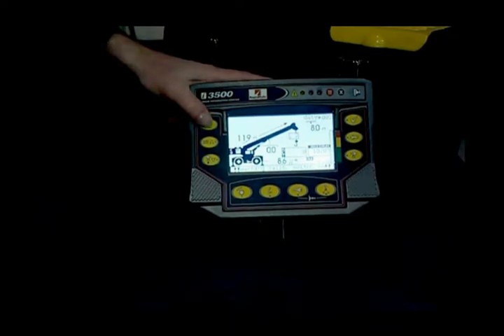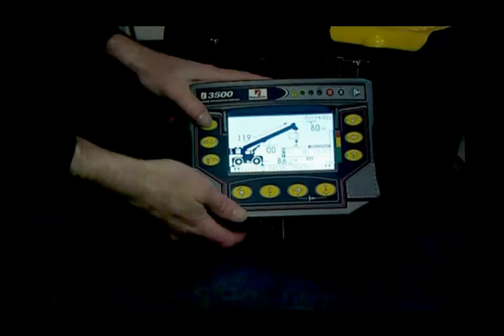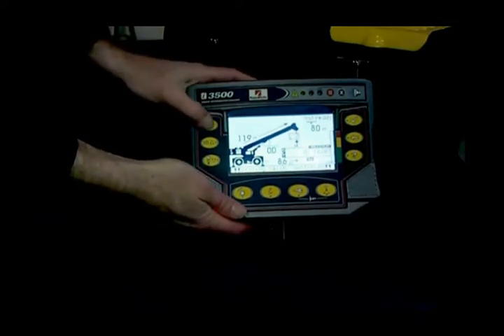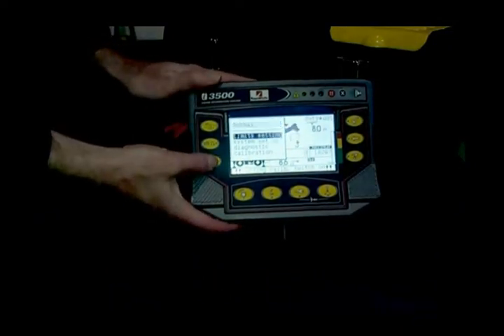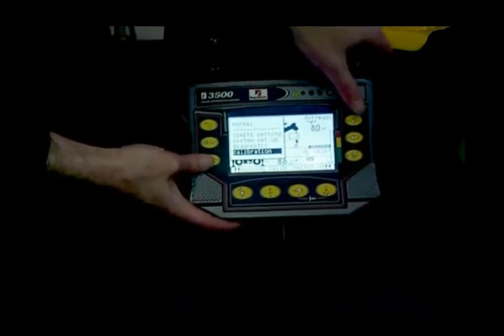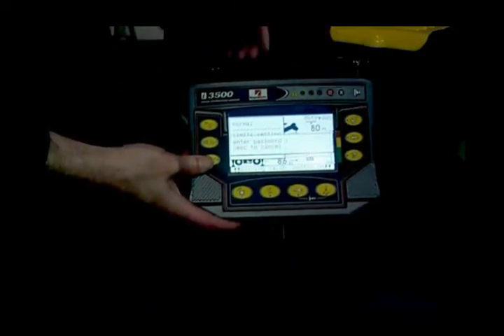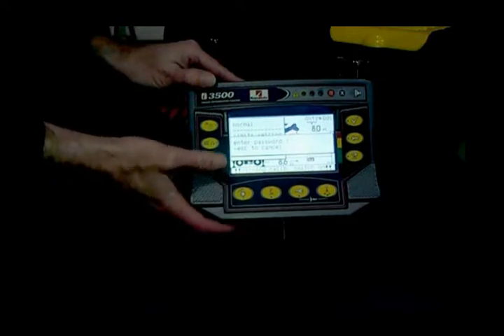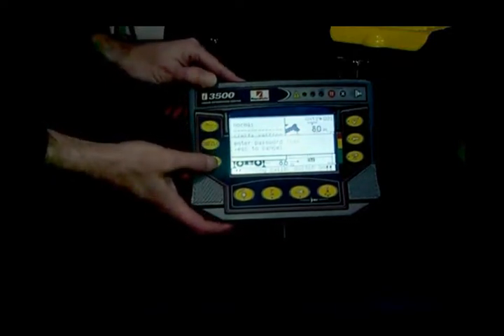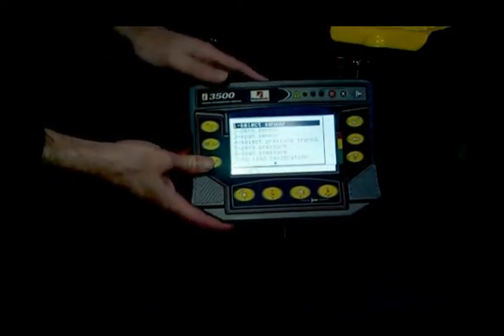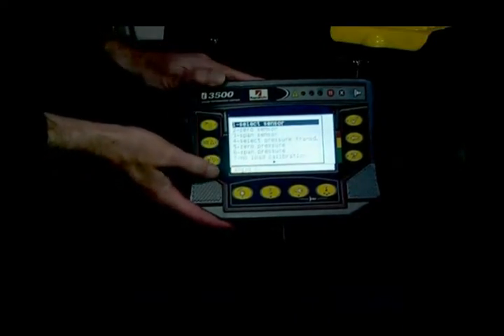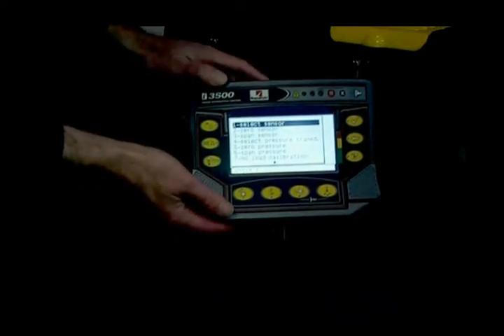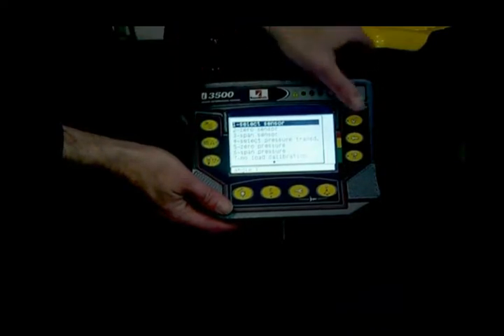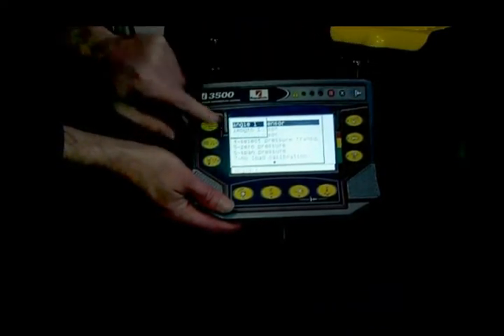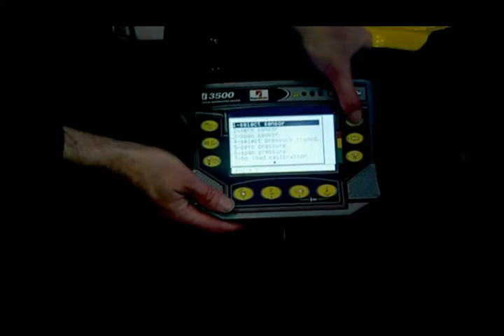So we know what the value is on our digital level, and now we want to go ahead and calibrate our system. So we're going to push button number 1, which is the mode button. We're going to scroll down and select calibration, hit the check mark. It's going to ask us for a password. The password is 1, 2, 3, 4. And that puts us into the calibration menu. So what we're going to do is calibrate the angle. So we're going to go to select sensor, make sure that angle 1 is highlighted, and hit the check mark.